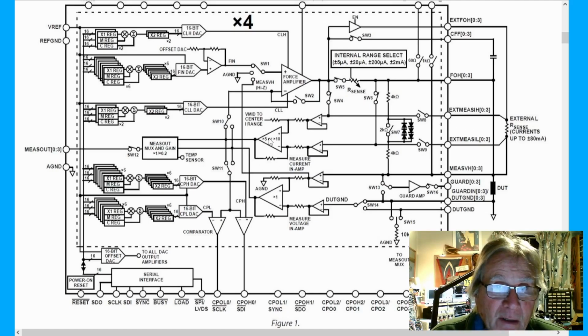This is the current sense amplifier with a gain of 5 to 10, and it's an instrumentation amplifier, and it either senses through S4 and switch 4 and switch 6 across the internal resistor, or switch 8 and switch 9 across the external resistor, depending on what current range you're in. Down here, the DUT voltage is sensed through the measure VH. I call that sense high. And then there's a signal called DUT ground, which is sense low, and then this instrumentation amp senses the voltage across the DUT and measures the difference between the plus and the minus. And then switch 10 here determines whether the current or the voltage gets fed back to the force amplifier. So in one way the system is a force voltage, and in the other way it's force current.